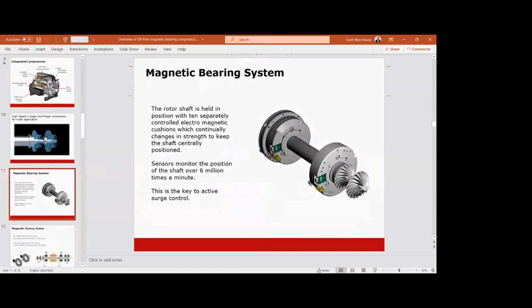Yeah. Okay. So the magnetic bearing system, the rotor shaft is held in position by permanent magnets. It is continuously controlled by electromagnets. So the heavy lifting is done by permanent magnets, and the electromagnets position the shaft to where we need to position it. The sensors look at the shaft over 6 million times to position the shaft correctly.